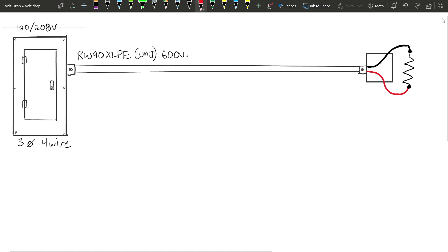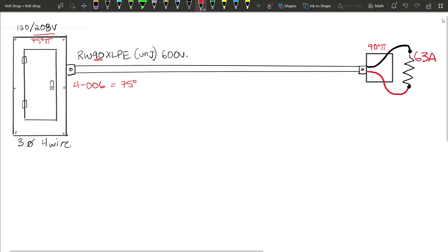Looking at this example, we're going with a 63 amp load fed from a 208 volt panel. We have 75 degree terminations in our panel and 90 degree terminations in our box. The first thing to keep in mind is when we have differing termination temperatures we always have to look at Rule 4-006 — in this case it tells us to go with the lower of the two, so 75 degrees.